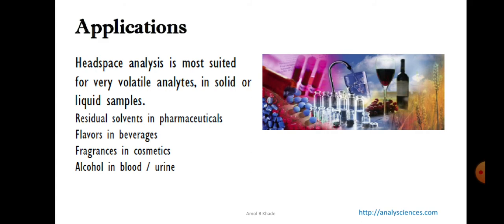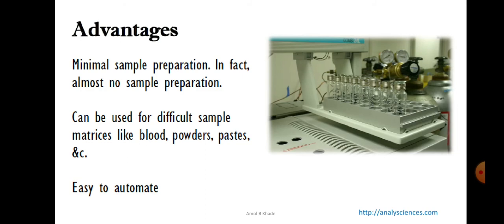This is very widely used in the analysis of residual solvents in pharmaceuticals, then flavors in beverages, fragrance in cosmetics, alcohol in urine or blood. The advantage of using this headspace analysis is it requires very minimal sample preparation. In fact, you need not do anything, just take your sample and put it in this headspace vial at half portion, and then your job is done.